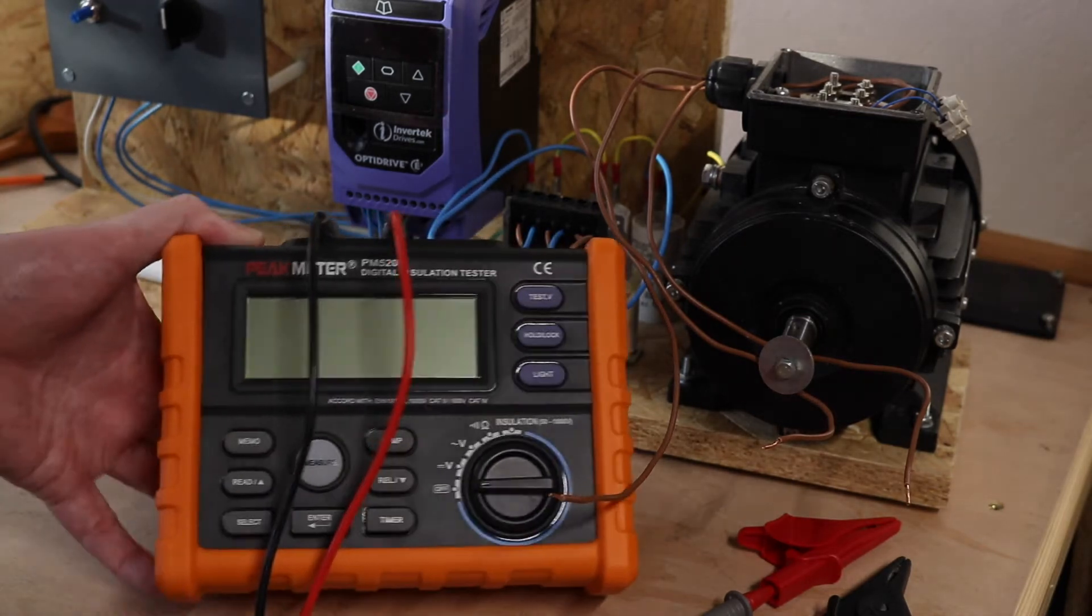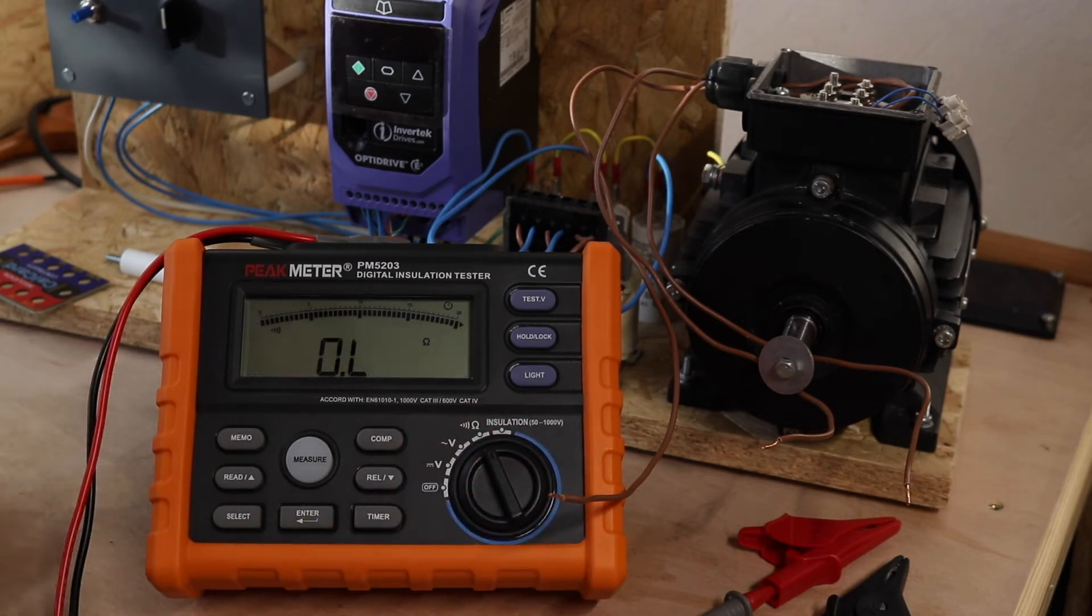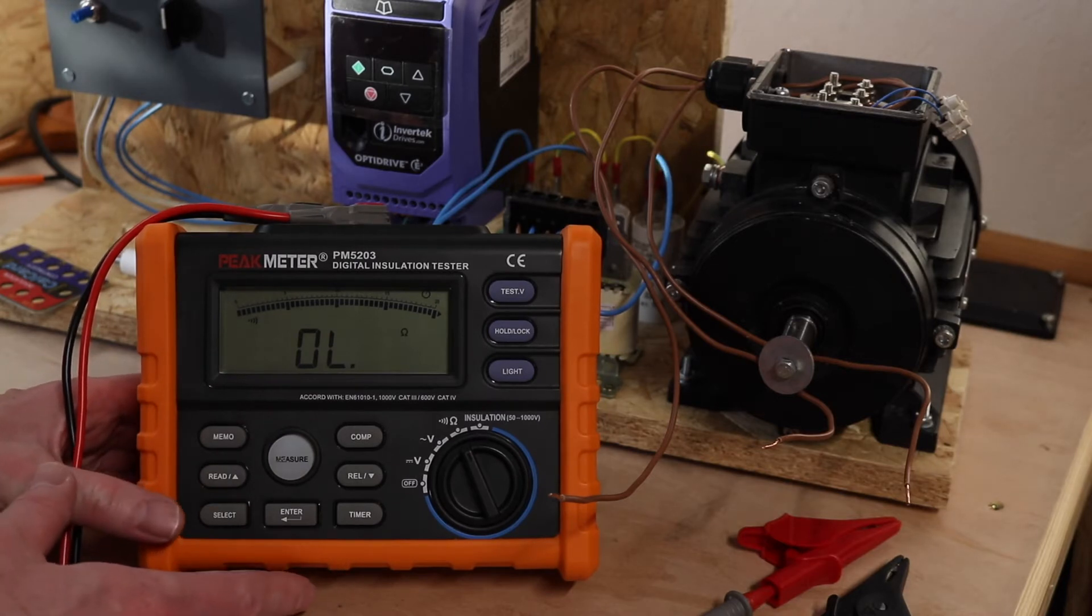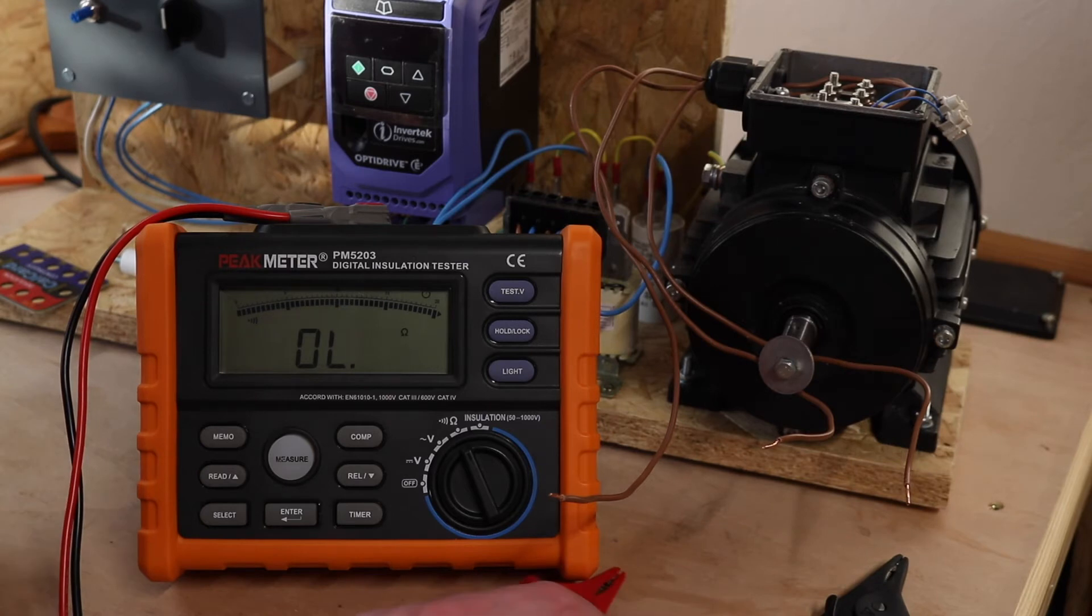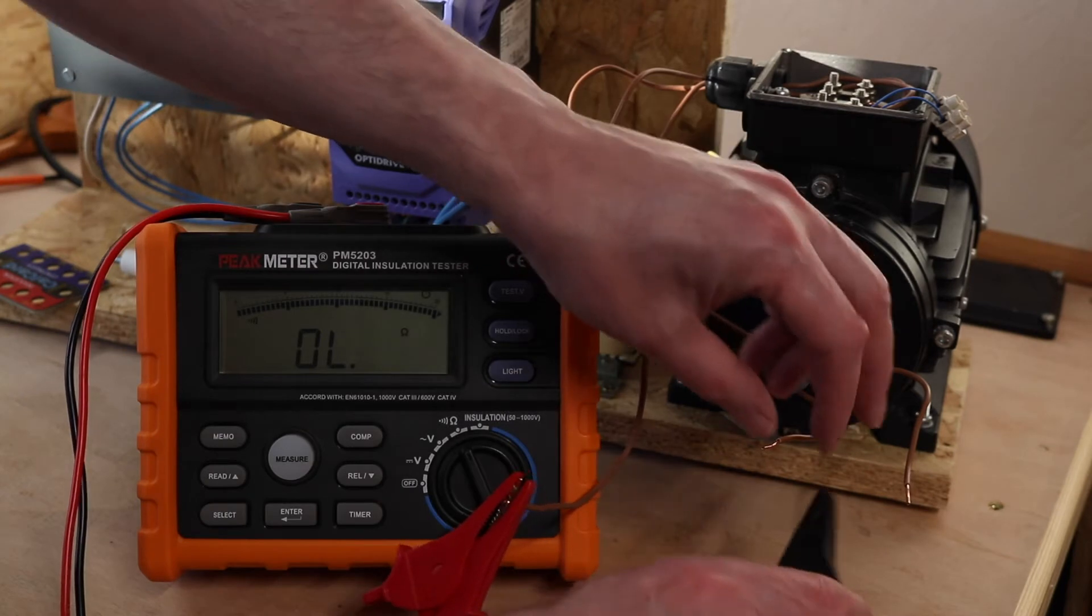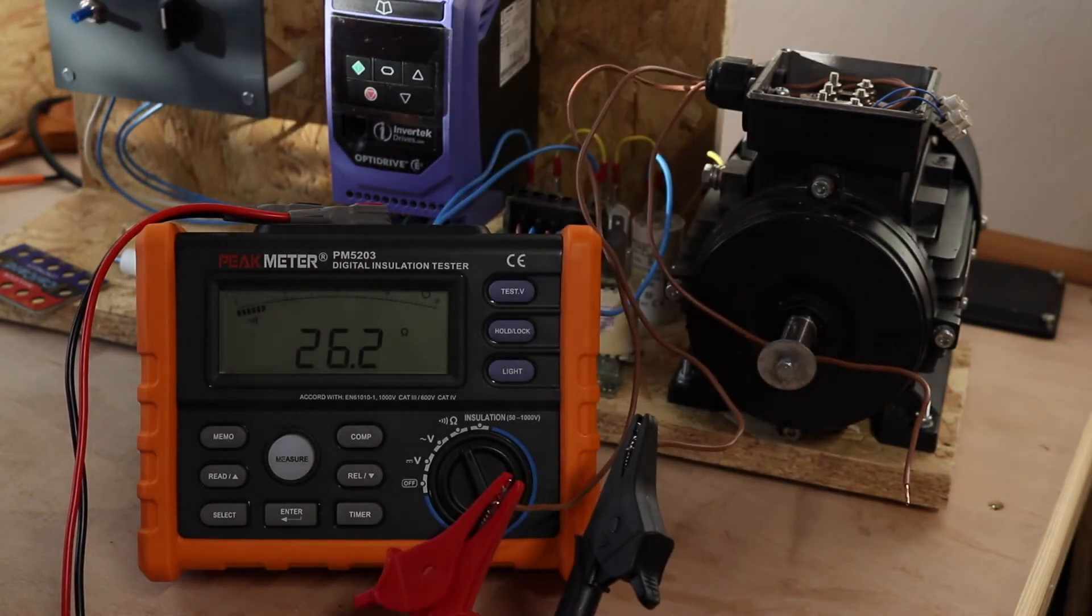To do that, I'm going to use the common terminal and the high V ohms continuity symbol terminal on the left of the instrument. I'll switch the instrument around to ohms continuity. This should be automatic, so I've got L1 to L2 and that's 26.2 ohms.